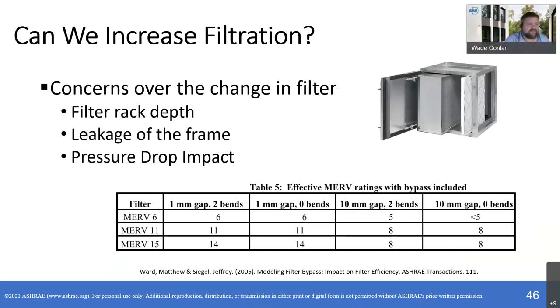So the bottom right corner, a 10 millimeter gap, which is 0.4 inch, operates like a MERV 8. Dr. Siegel is quoted in some articles as saying, I'd rather have a well-installed MERV 11 than a poorly installed MERV 15. So what we do recommend to facilities owners is for their filter changing crew to do an integrity test, like you would do on lab or BSL3 exhaust, to make sure the filters are installed well and capturing. Do it on one of your air handling units after they change the filters. Do an integrity test, see what they need to do differently so that they can make sure they're installing them well. It's a key component to having filters, is how well they're installed. The next slide, please.